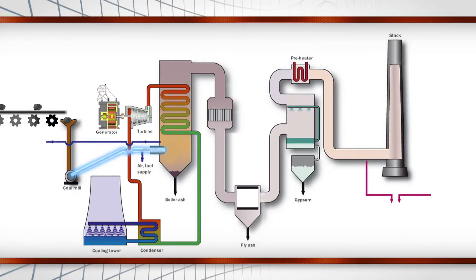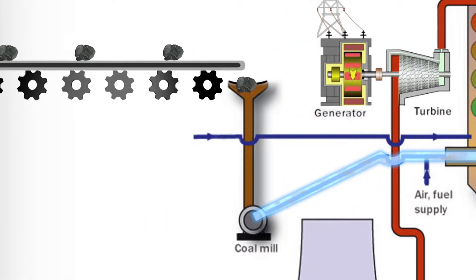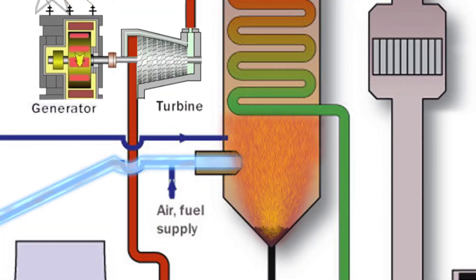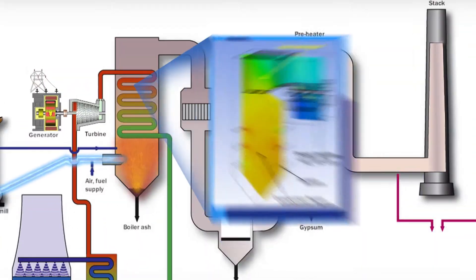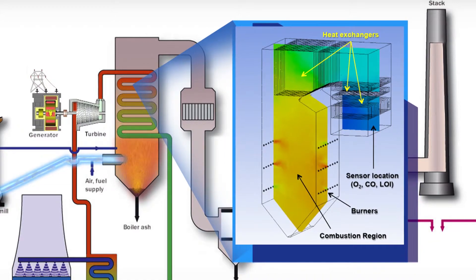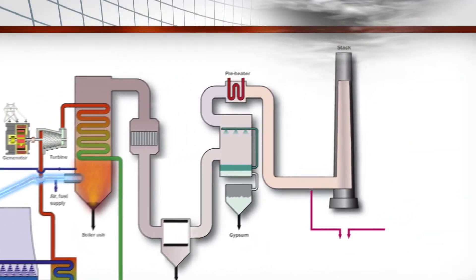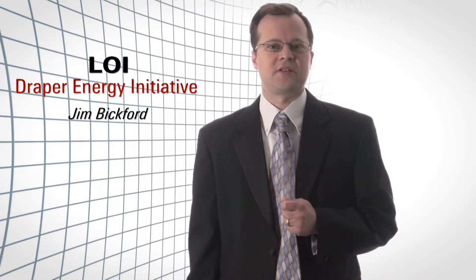Let me give you a little background on how coal power plants actually work. Coal starts as solid particles, gets ground down into dust, combined with air, and blown into a large furnace — think of it as a 15- to 20-story building hollowed out with a tremendous fireball in the center. The flow is pulled out and goes past heat exchangers that remove energy to boil water, which drives a steam turbine that generates the power. On the back side of the plant, they remove contaminants and pollutants before exhausting to the atmosphere, and this is where different types of sensors are placed.